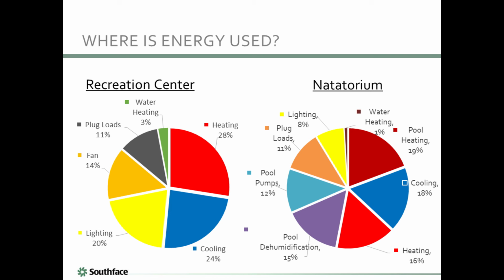So based on the assessments that were performed on these 6 recreation centers, these are the energy use breakouts. The energy use shown in these charts is source energy. The 5 recreation centers that did not have a natatorium are shown on the left. Recreation center with a natatorium is shown on the right. You can see on a typical recreation center without a natatorium, heating is the highest end use, followed by cooling. So heating and cooling represent about 2/3 of building energy use. And lighting represents about 20%. Plug loads represented around 11% of annual energy use, and water heating, even in facilities that had an outdoor pool and shower facilities, was very low at only 3%.